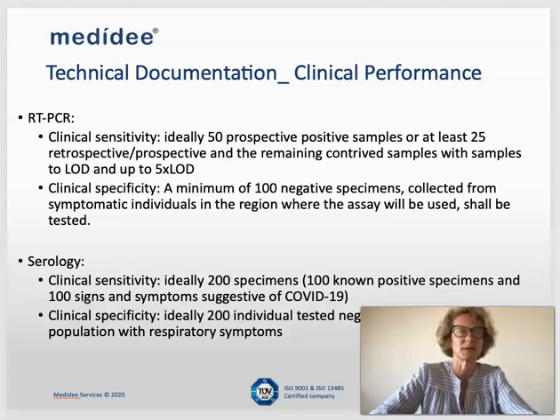Here you see that for molecular tests, to calculate the clinical sensitivity, you need at least 50 samples. Ideally they would be prospective, but this is often not the case. So it is also said that you can use 25 retrospective or prospective samples, and you can also use contrived samples which are around the LOD and a bit higher than the LOD. For the clinical specimens, for molecular tests, a minimum of 100 negative samples collected from symptomatic patients is requested.